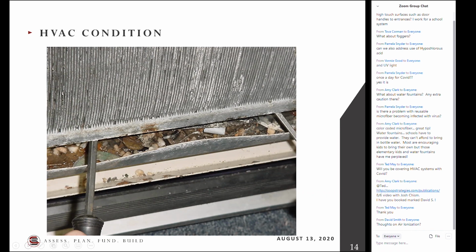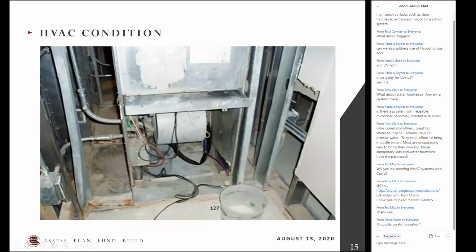And from the complaints that I get from residents and other people, one of the number one complaints is my air conditioning flooded. One of the previous speakers was talking about how they were very careful with their fan coil units to make sure the condensation drains were working and everything was clean and tidy. That is a preventive maintenance issue, and you've got to keep the water draining out of the drip pans underneath units. In this picture, you can see the black tubing, that's the condensate drain, and they kinked it. So you're going to have a flood there eventually.